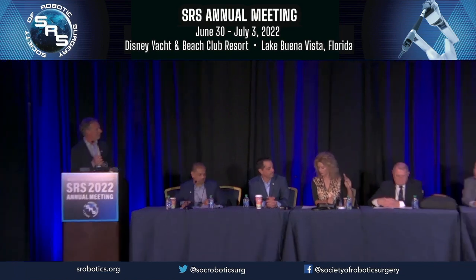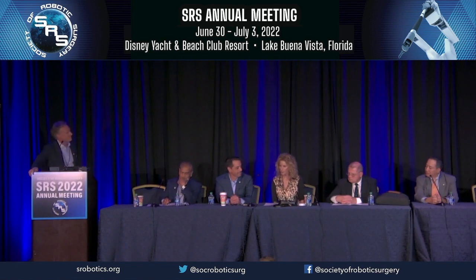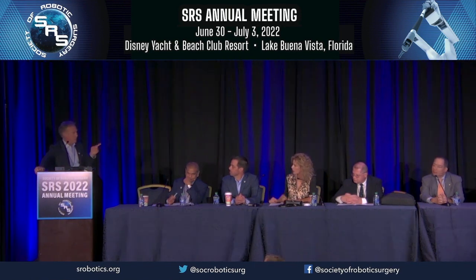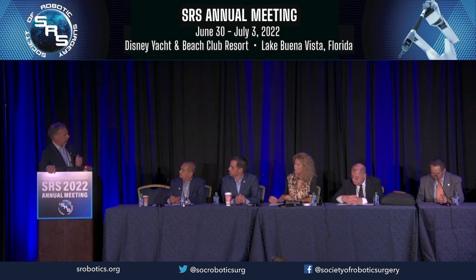A couple of questions for our panel. This system is for single incision, but right now it's not fully single incision because the scope is coming through another incision. We understand our core competencies are robotic technology, so we are not releasing this first application with our own vision system — we are scope agnostic. You can use whatever system you currently use. The two arms that do the work are through a single incision, and we do have one incision through the umbilicus for a camera at this point.